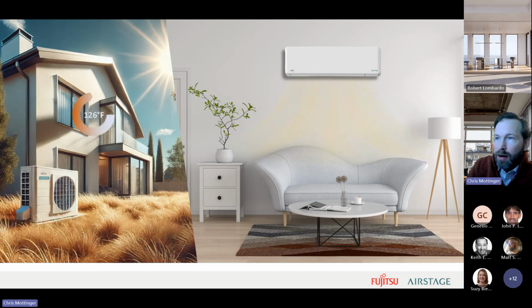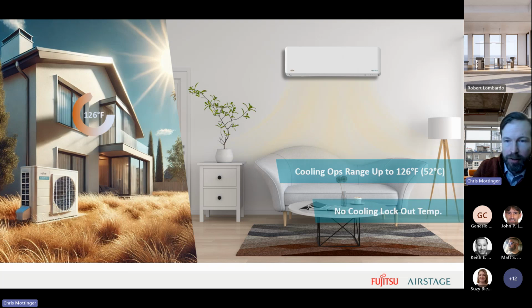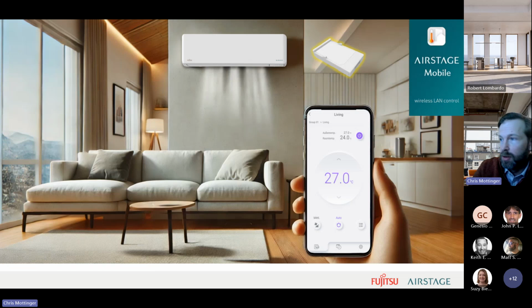And what you'll notice is that on these wall mount systems, on these newer products, we rate the cooling up to 126 degrees outdoor temperature. As we all know, here in Pennsylvania and New Jersey, we don't get up to 126 degrees, but down south, they do. And formerly, Fujitsu was not rated for that high of a temperature outdoor. We have no high lockout on our cooling operation now for Fujitsu as well. So if we run into those high ambient operations for any reason, we will still provide mechanical cooling even above the temperatures that we post on that slide.